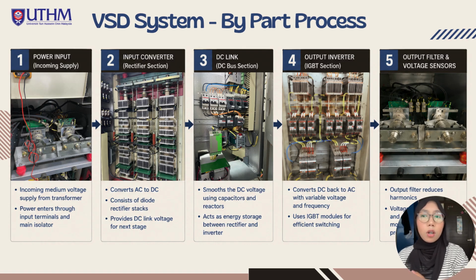Next, this slide shows the internal operating stages of the ABB ACS 1010 variable speed drive. The process begins at the power input section where medium voltage AC power enters the drive. The input converter then converts AC power into DC power, and the DC link smooths and stabilizes the DC voltage while acting as a temporary energy storage. The output inverter converts the DC power back into AC power with adjustable voltage and frequency. Finally, the output filter and sensors reduce harmonics and continuously monitor system parameters for protection and control purposes. Lastly, this process allows precise control of motor speed while maintaining efficient operation.